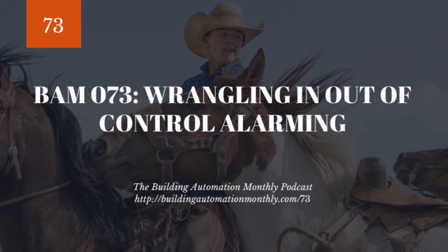Because that is kind of the nightmare of facility management - if you get into this death spiral where you can't keep up with the maintenance faster than the issues are occurring, that's when you start to see these Band-Aid solutions. That's when things really start to fall apart. You find 2x4s, you find holes cut in ductwork, you find valves with the actuators taken off them, just permanently set at like 80%.